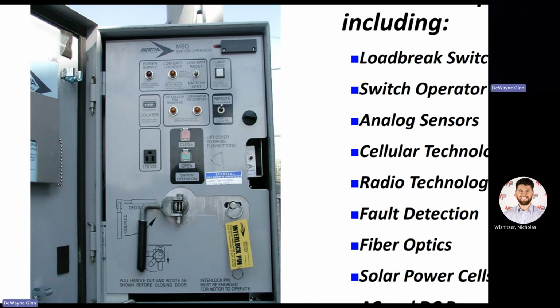Up at that bar, that black bar up in the right, that's a sensor for the door. So when I open the door, it goes back to the control house and says somebody has entered this cabinet. There's a rain gutter on top, so if there's rain or moisture, it's not going to fall down on you. I have a lamp tester. I can test all the lamps in it. There's also a power supply low battery lockout. What that low battery lockout means is, if I do not have enough voltage in the battery and it's set, it will lock out the motor operator and not allow you to operate the switch.